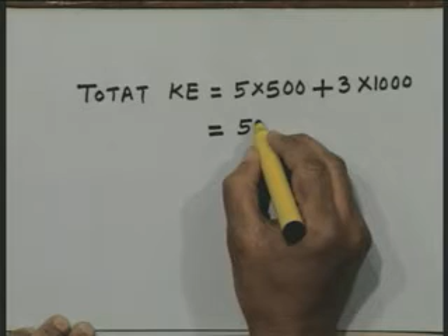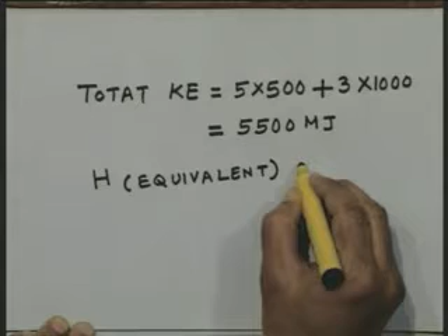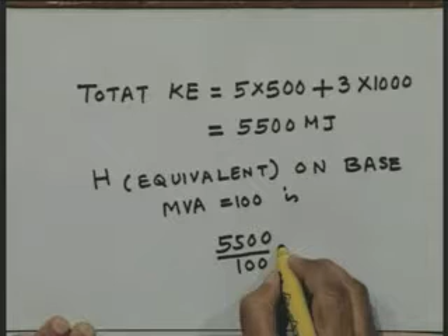Therefore, I can say the equivalent H on base MVA equal to 100 is 5500 divided by 100, because base MVA is 100. It comes out to be 55 megajoules per MVA. This is the way one can find the equivalent inertia constant of a number of machines which are running in the same plant and are coherent.